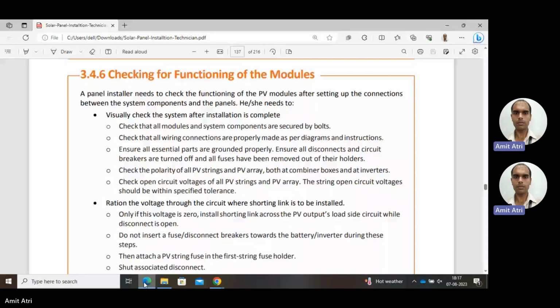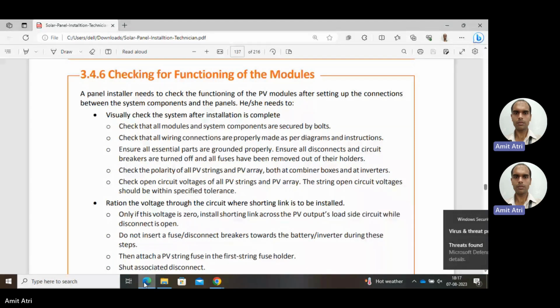Okay, after completing the installation process, the solar PV installer needs to check for the functioning of the modules. Means the system and the different components which are connected, they are properly functioning. This the installer has to ensure. So the installer needs to visually check the system after installation is complete. They should check that all modules and the system components are secured by bolts. Means proper fixing, proper installation is there.